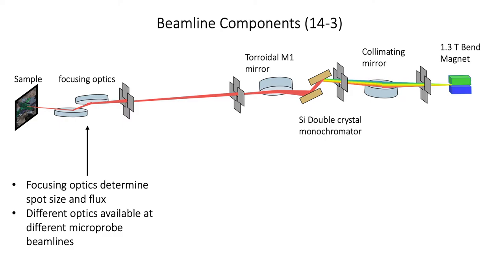Let's take a look at the different beamline components — this example is from beamline 14-3, though it's illustrative of all our micro imaging beamlines. At 14-3, x-rays emanate from a bend magnet, then go to a collimating mirror and from there to a silicon double crystal monochromator. All of our beamlines at SSRL offer a 111 double crystal monochromator; however, beamline 6-2 additionally has a 311 monochromator option which provides higher energy resolution. The beam then goes to a toroidal focusing mirror, into the hutch through aperturing slits, and finally to the focusing optics and onto the sample.